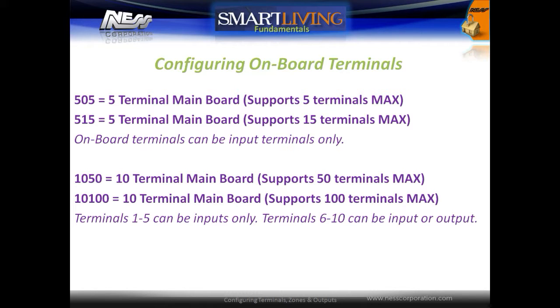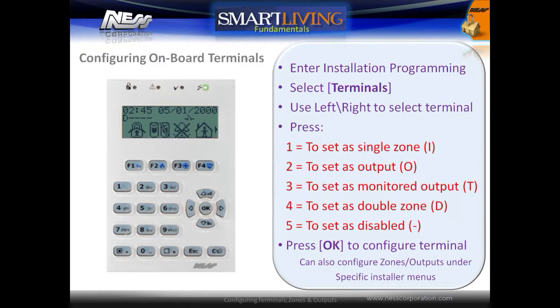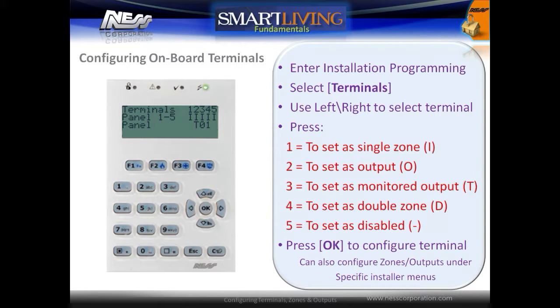To configure the onboard terminals, enter into installation programming and then select the Terminals menu. Use the left and right arrows to select a terminal, and use numbers 1 through 5 to set the terminal type. Once the terminal type has been set, press the OK button to configure the terminal. Terminals can also be configured under Zones or Outputs in installation programming.